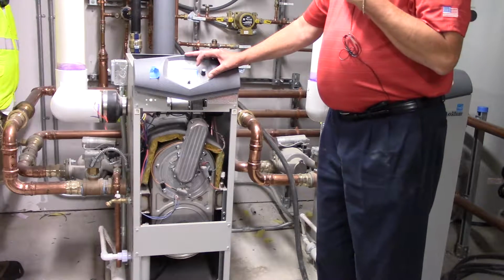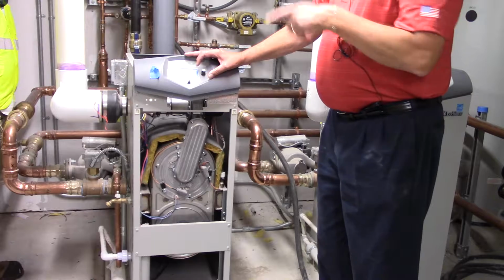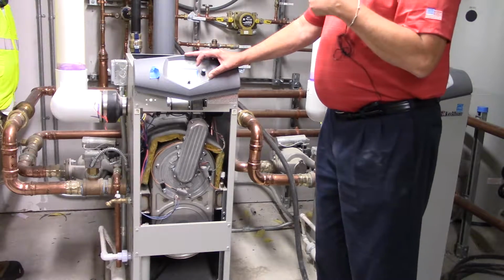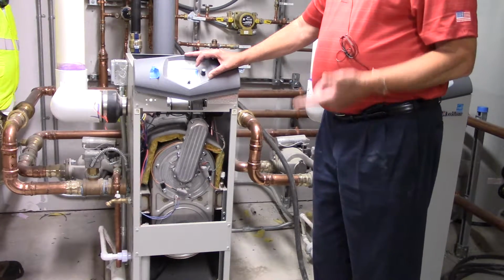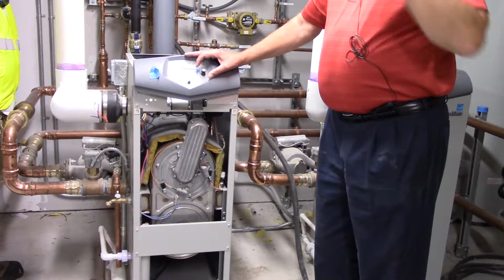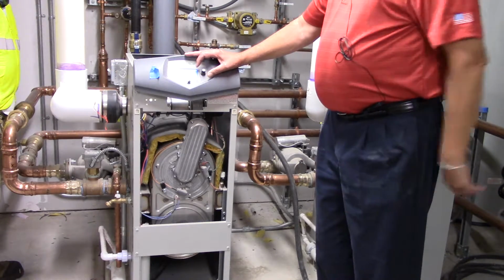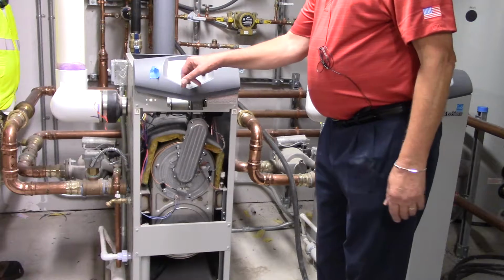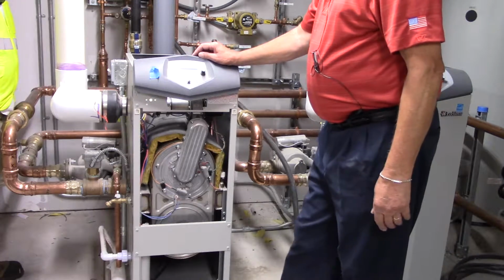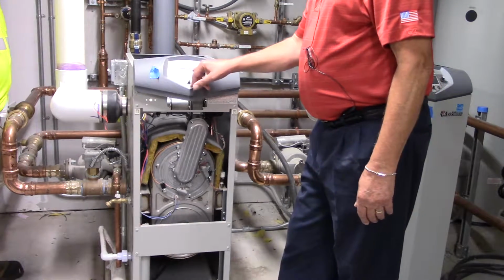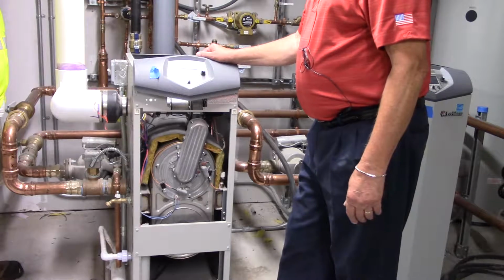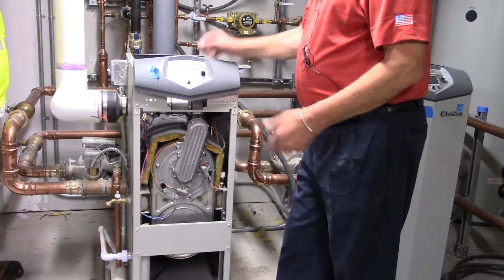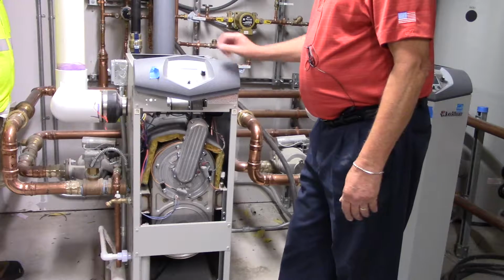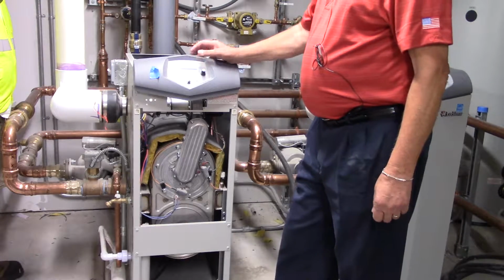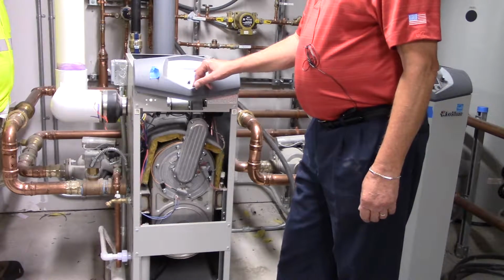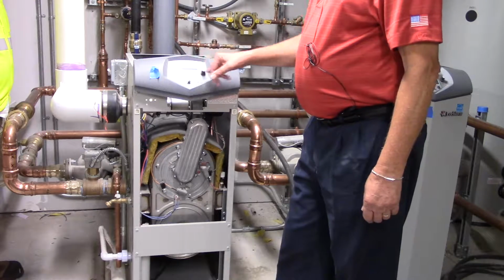I'd recommend you got 2 of these units here, and I know you got at least 6 others around here, that you have a sensor and an igniter. It's short money, and it'll just save you a trip the day that you need it. So this is firing right now at 30%, and you can see this. The signal is rising. It's 8.4, and by the time it gets up to 100, it'll be probably 12 to 14. It's going to tell you what your fan speed is as it relates to the firing rate.